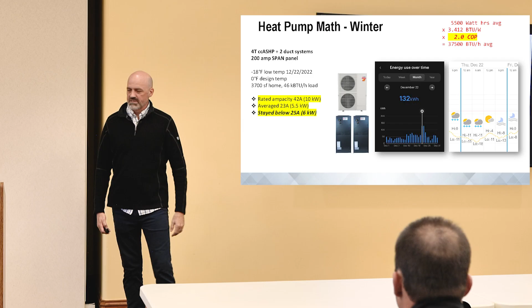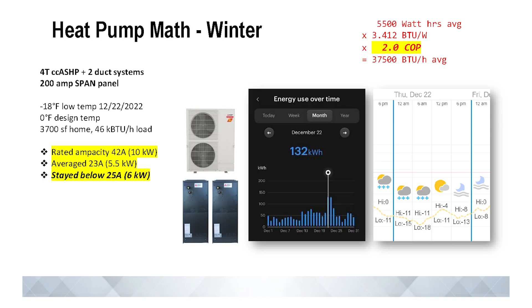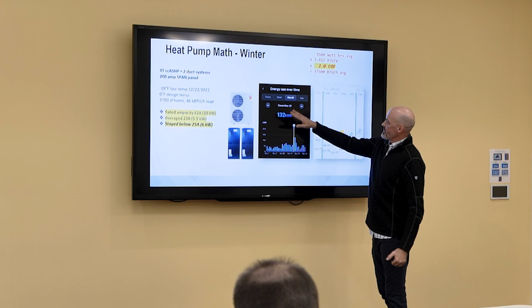Overall, top right corner, here's the math: 5,500 watt-hours average over this one day. I couldn't drill down any further than this. That's 132 average through the day because it was a cold day — here's the weather for the day. 5,500 watt-hours times BTUs per watt times a COP of approximately 2, which is roughly how this system was operating — you'll just have to trust me on that number for now.